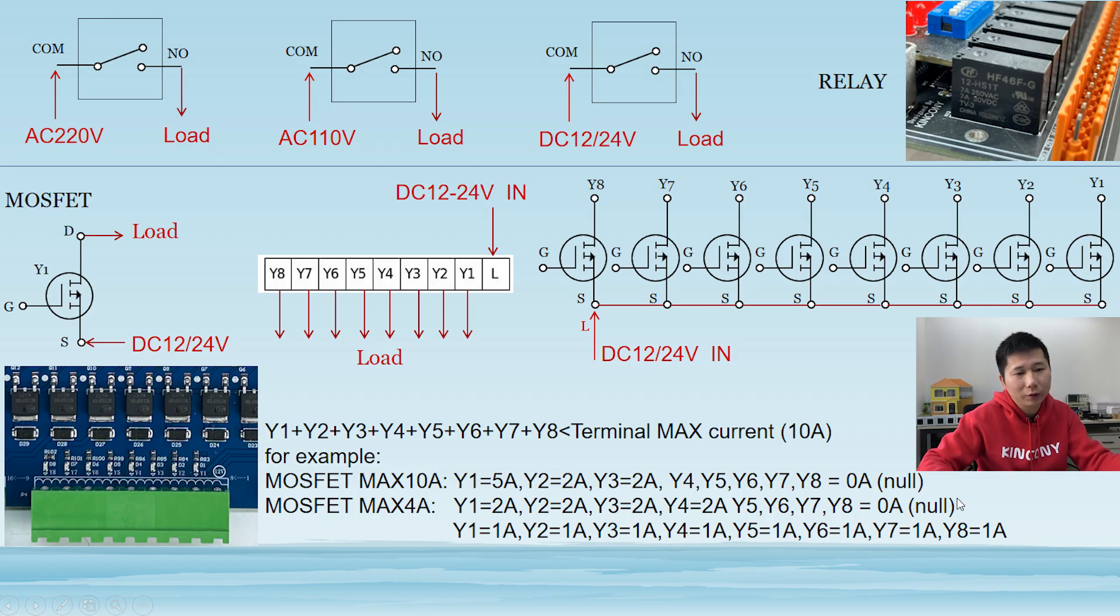Okay, you can see, if the second example, that, Y1 is 2A, Y2 is 2A, Y3 is 2A, Y4 is 2A. So, this can add together, is 8A. So, make sure, your Y5, Y6, Y7, Y8, have a smaller current, just, not, greater than 10A.